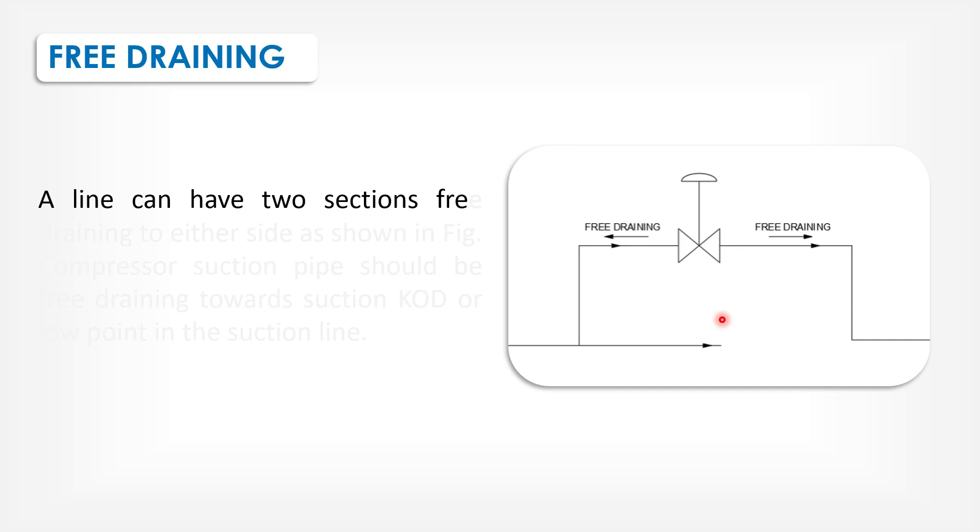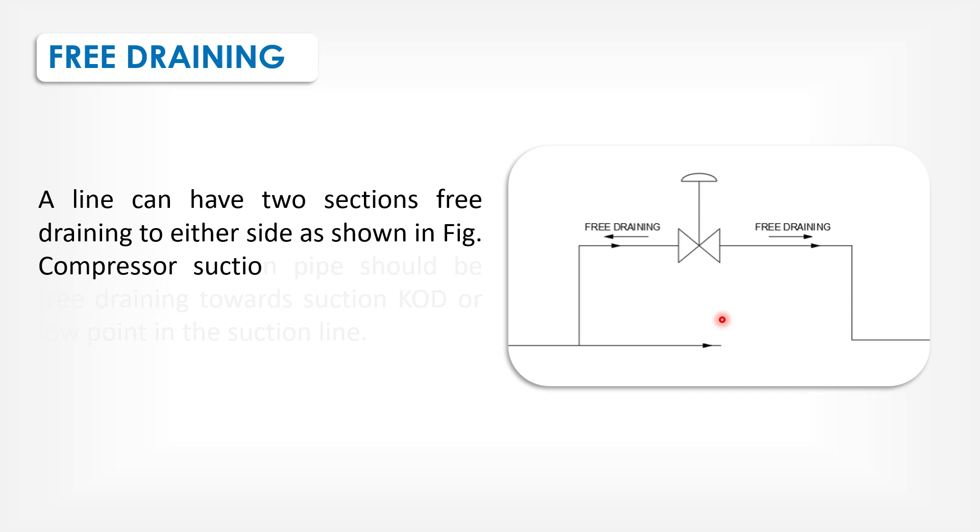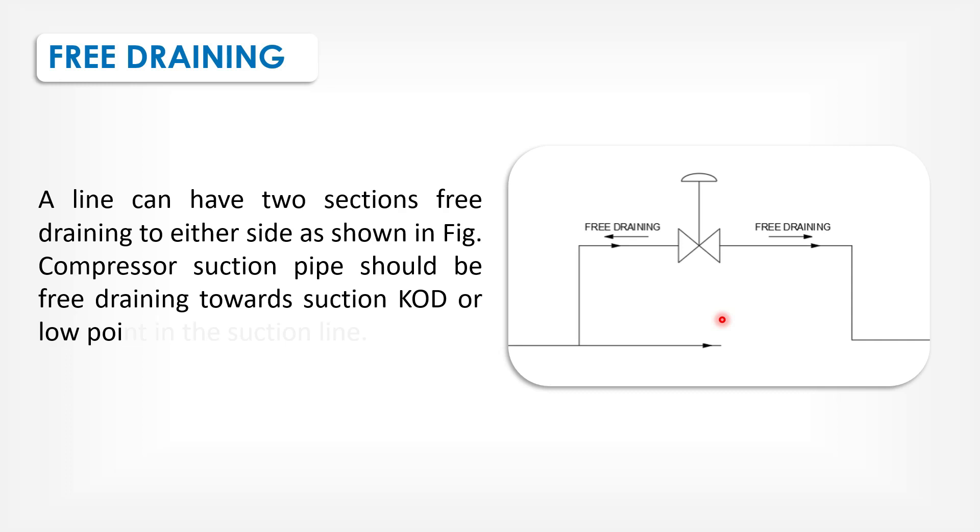A line has two sections free draining to either side as shown in the figure. Compressor suction pipe should be free draining towards suction knockout drum or low point in the suction line.